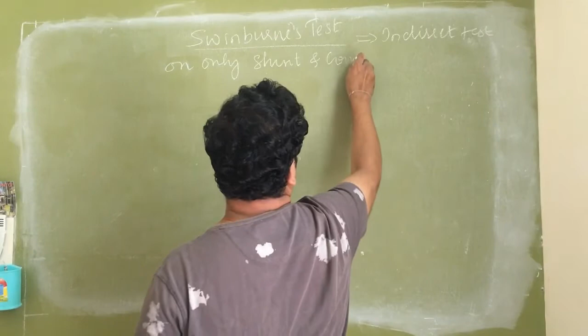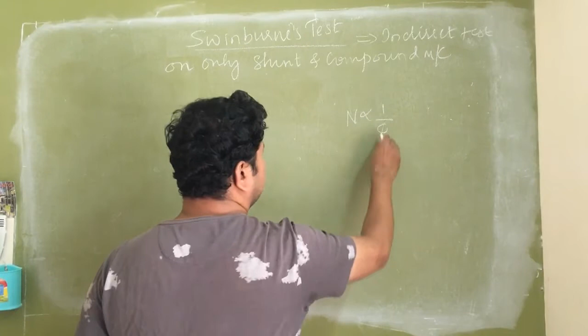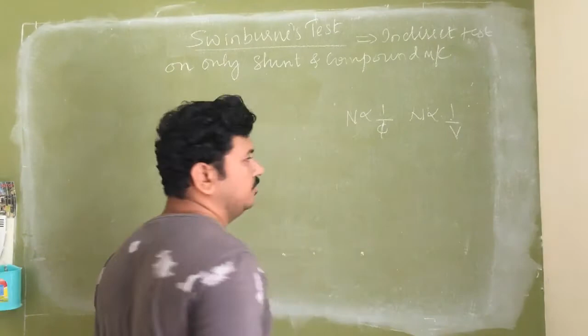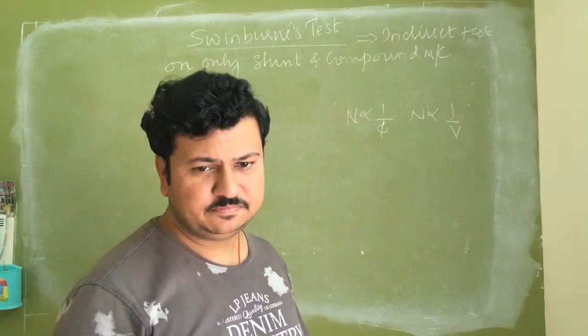The indirect test is to be conducted only on shunt and compound machines. It is compulsory. I can't do Swinburne's test on a series machine. Why? Because it is an indirect method, so I will not load the motor while testing, and a series motor cannot be started without load. N is inversely proportional to phi. For a shunt machine, N is inversely proportional to voltage, because flux in any machine is always proportional to voltage.